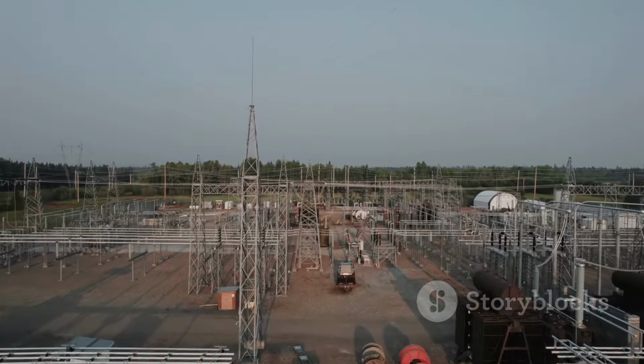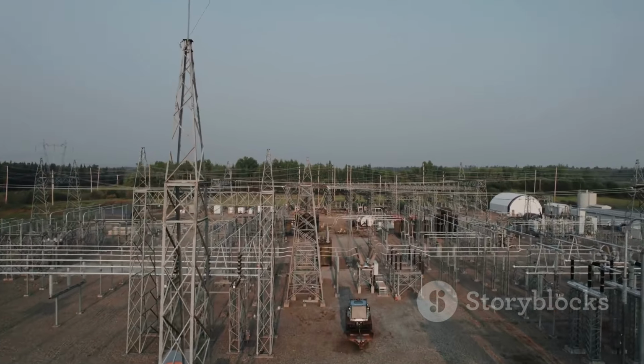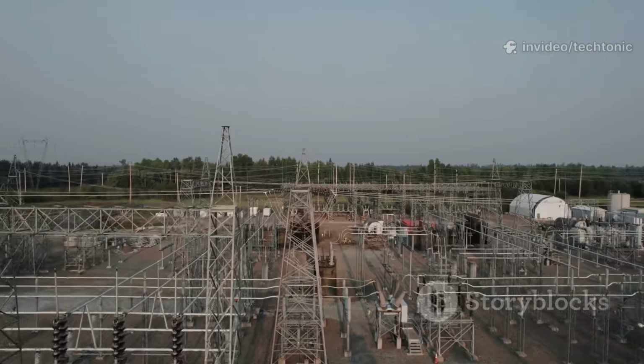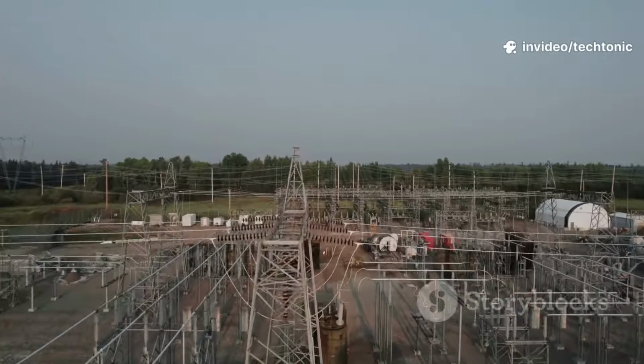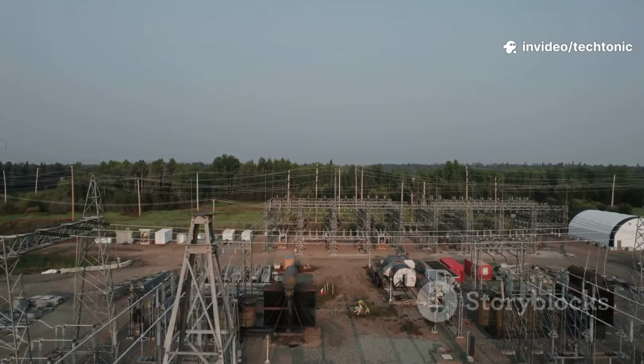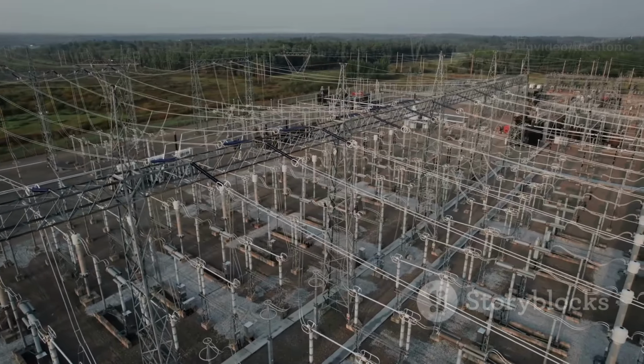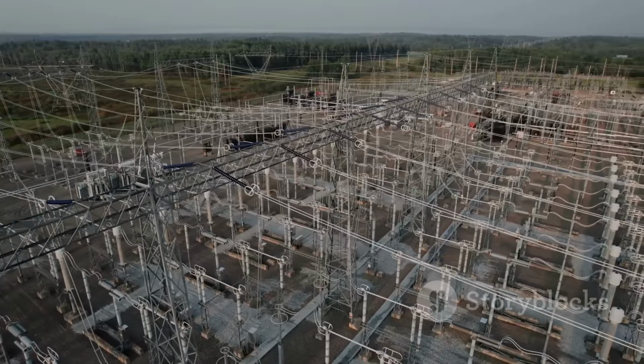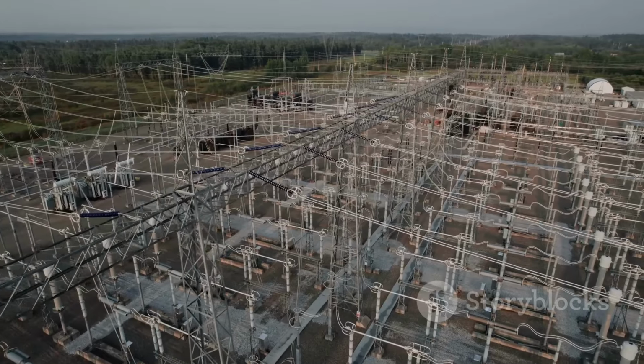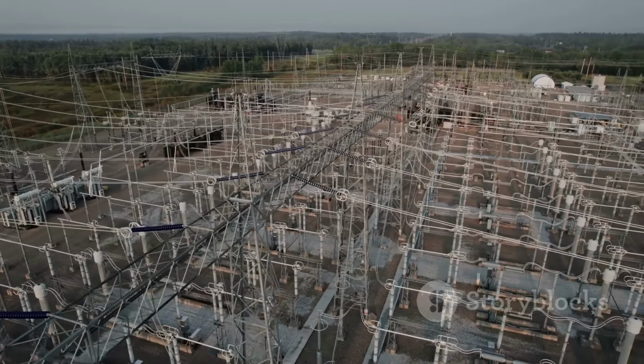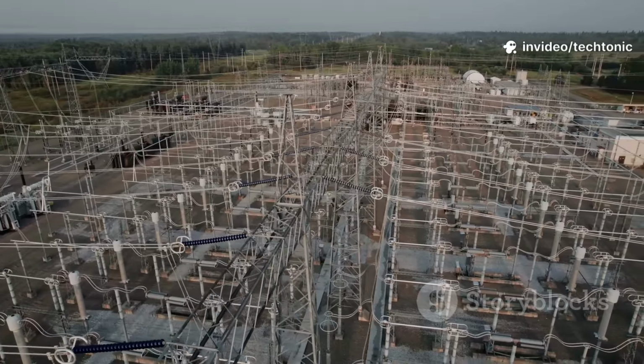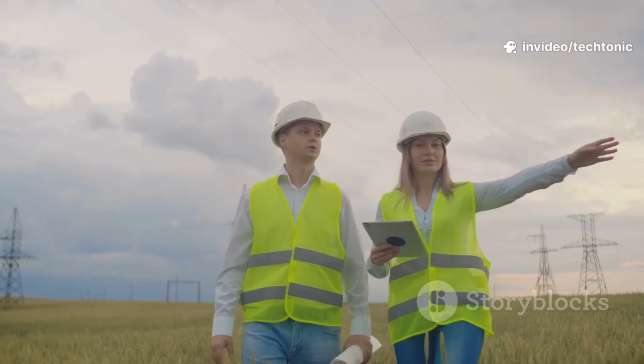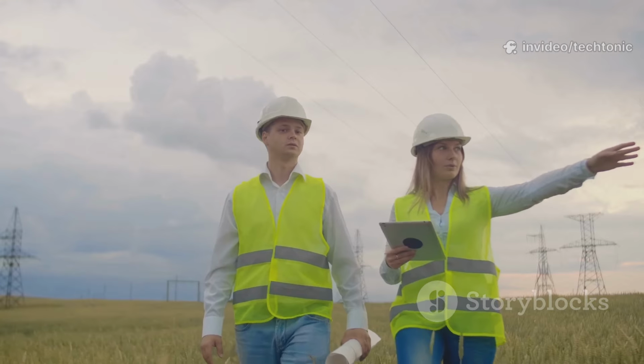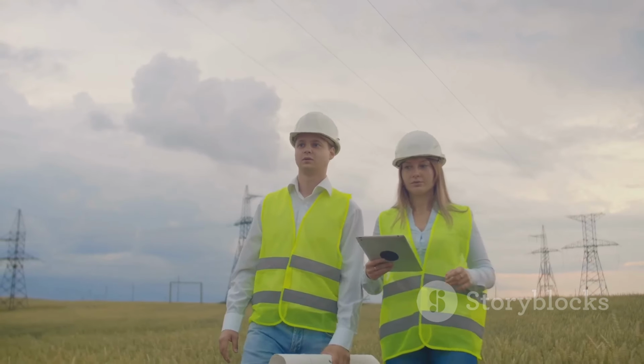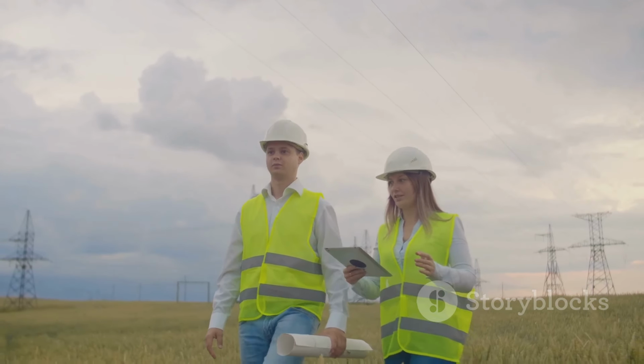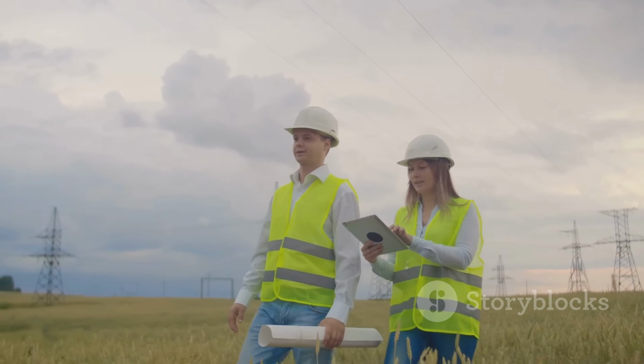Another strange issue with long HVAC lines is known as the Ferranti effect. Because the long transmission line acts like a giant capacitor, it can cause the voltage at the receiving end of the line to become higher than the voltage that was sent in the first place. This might sound like free energy, but it's actually very dangerous and can damage the expensive substation equipment that's waiting to receive the power. To combat this, engineers have to install special equipment called shunt reactors along the line to absorb the excess reactive power and keep the voltage stable, adding to the overall cost and complexity of the system.